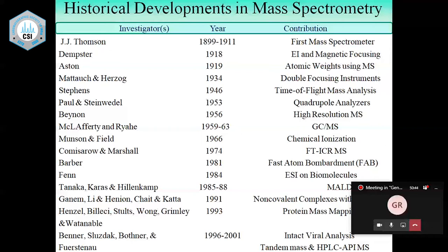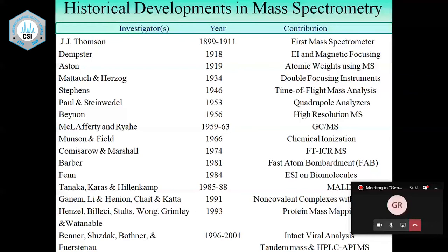In FT-ICR MS, in contrast to conventional mass spectrometry, everything — ion generation, analysis, and detection — takes place in a small cubic cell placed in a very high magnetic field of more than five tesla. Image currents are produced from which you get the mass spectra. It is a very complicated mass spectrometer, so it is confined to research laboratories, but it provides very high resolution — millions of resolution.